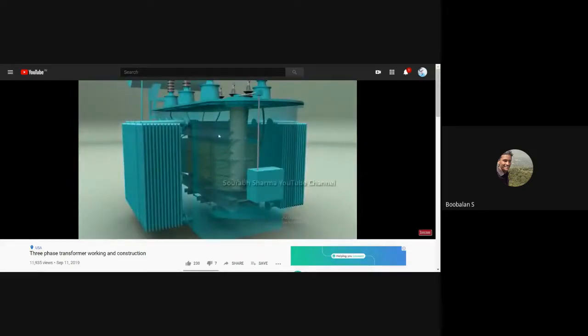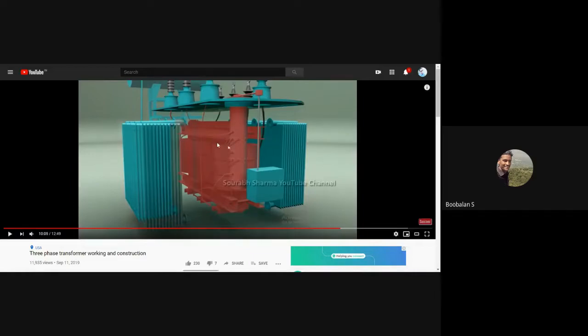During working condition, a lot of heat is generated in the windings of the transformer due to copper loss and dielectric loss, and also due to hysteresis and eddy current loss that occur inside the metallic core. The generated heat is transferred to the transformer oil and the oil gets heated up. Due to natural convection, the heated oil rises up and gets into the radiator wings through these vents at the upper side, and the heat of the oil is transferred to the environment through the radiator wings, and the cooled oil comes back into the main tank through the pipes at the lower side of the radiator wings. This process of natural convection continues by itself naturally.